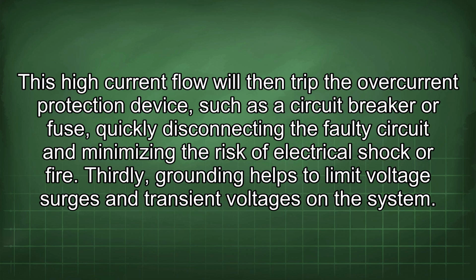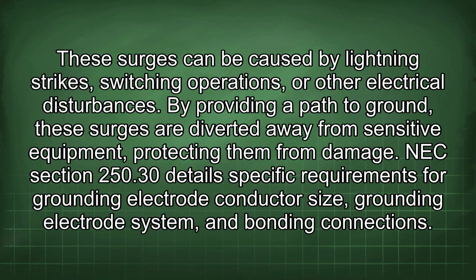Thirdly, grounding helps to limit voltage surges and transient voltages on the system. These surges can be caused by lightning strikes, switching operations, or other electrical disturbances. By providing a path to ground, these surges are diverted away from sensitive equipment, protecting them from damage.